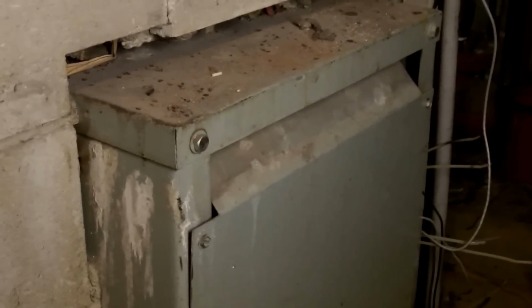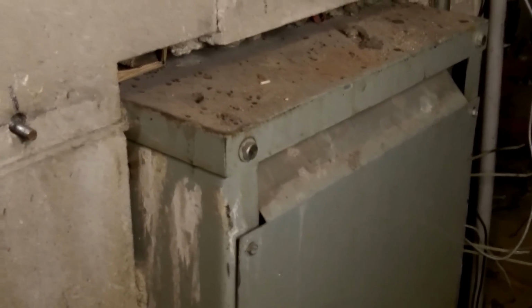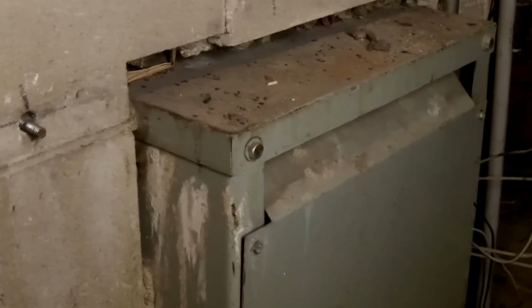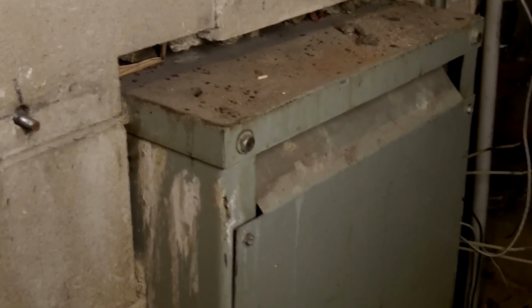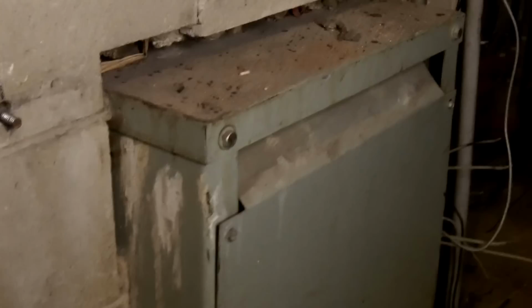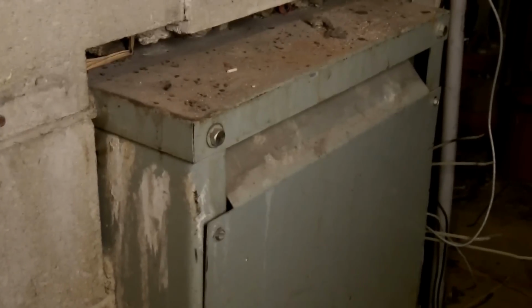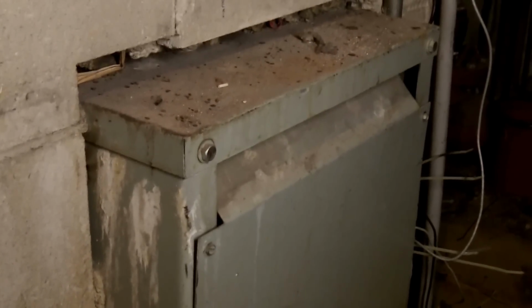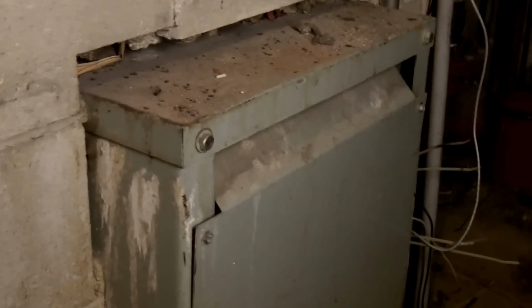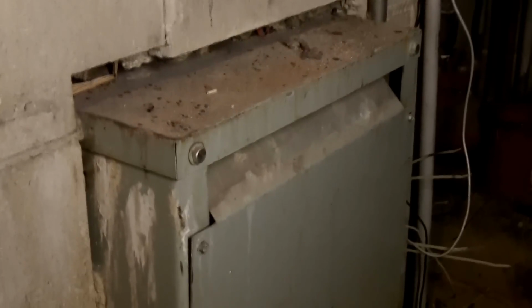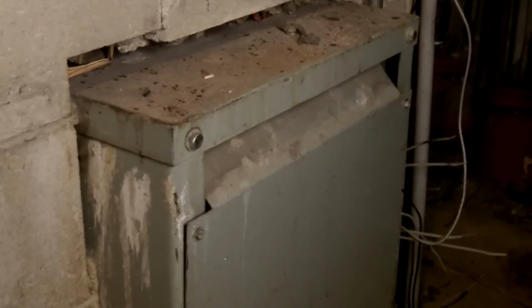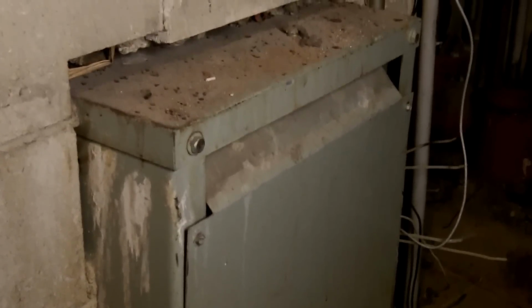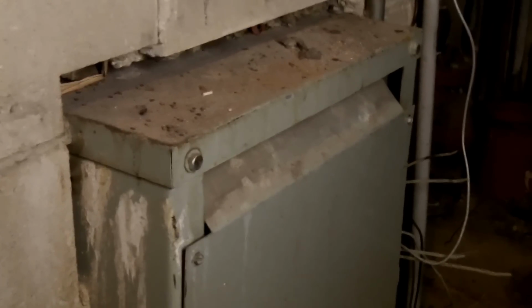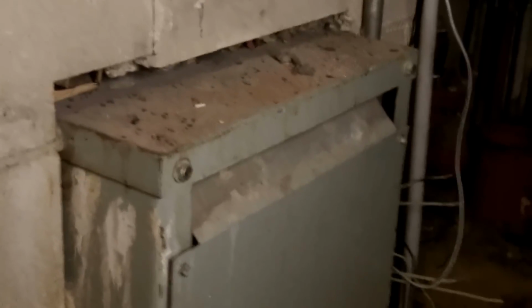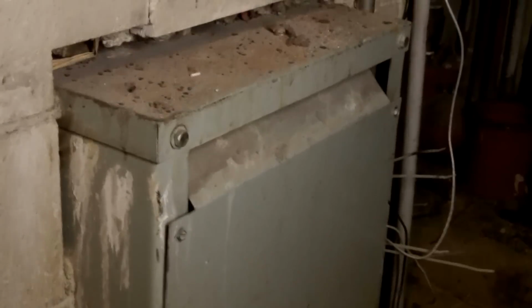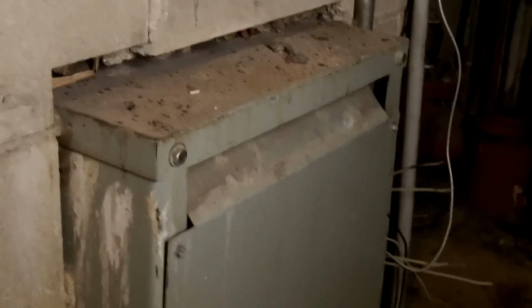This is a violation of NEC section 110.13B, which requires that when equipment depends on the circulation of air for cooling, it has to be installed so that the airflow isn't prevented by walls or adjacent equipment. In this case, we can see that the walls obstruct the free circulation of air through the equipment, and that's going to cause the transformer to run hot and eventually break down the wiring inside the transformer.